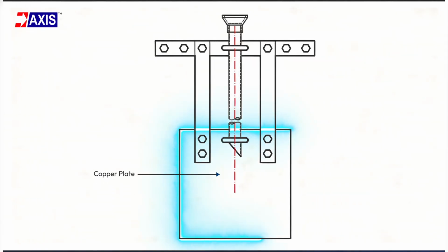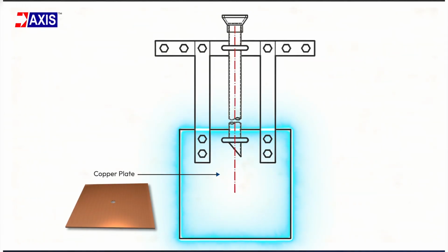First of all, starting with the plate. A copper plate is the main electrode used in plate earthing. This is the part that goes into the soil and provides the contact area for fault current to enter the ground. When a fault happens, the current travels down the earth strip and enters the soil through this plate. The large surface area helps the current spread quickly and lowers the overall earthing resistance. In plate earthing systems, copper plates are commonly available in sizes such as 600 by 600 mm with thicknesses like 3.15 mm or 6 mm. This plate is also available in galvanized iron, having a size of 600 by 600 mm with thickness of 6 mm. However, you can customize it depending on your project requirements.